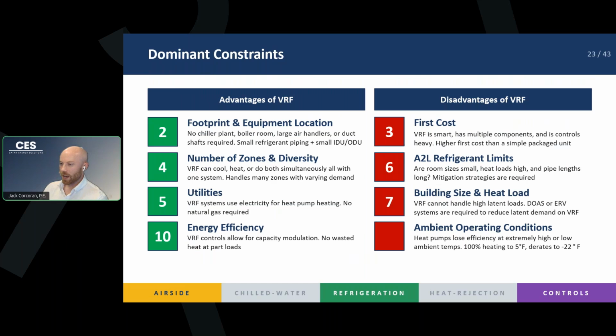And lastly, this one doesn't have a number because it wasn't on our list of 10. As I said, there are way more than just 10 constraints you got to think about. But in this situation, for VRF, we got to think about our ambient operating conditions, right? Because we are using heat pumps, and we're using pressures and we're manipulating our pressure to get the right temperature so that we can absorb and reject heat.